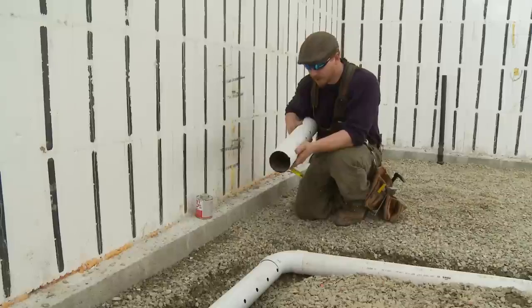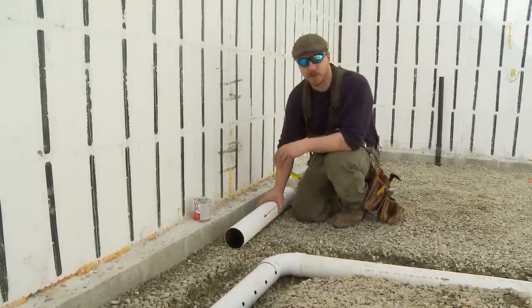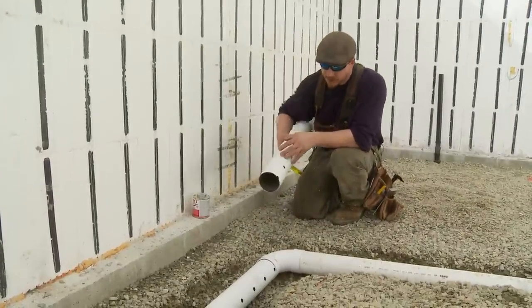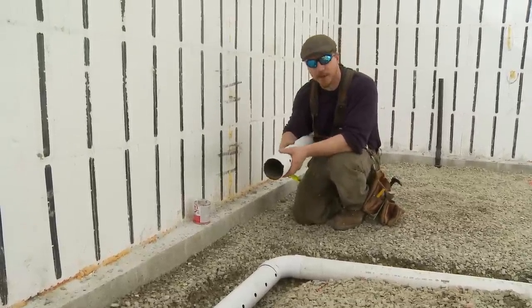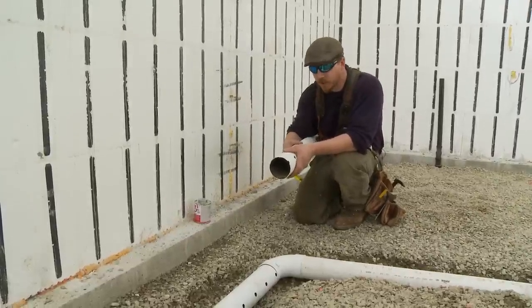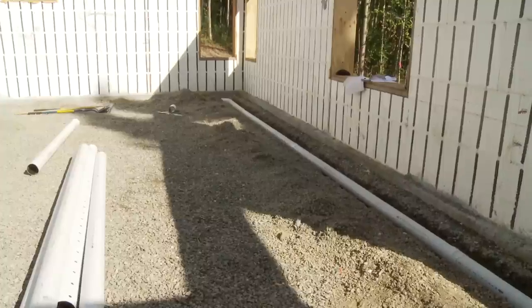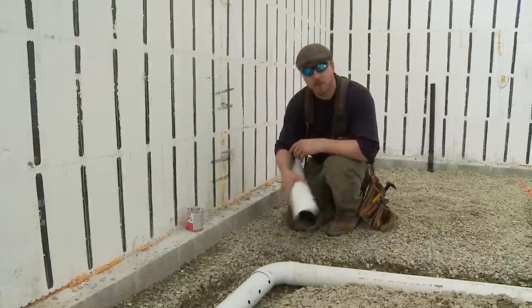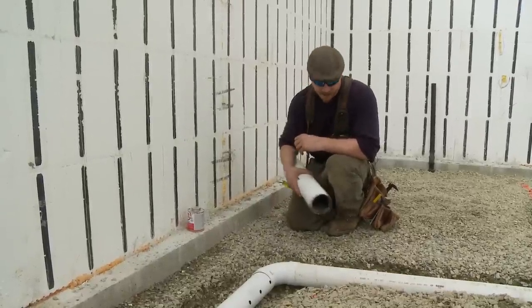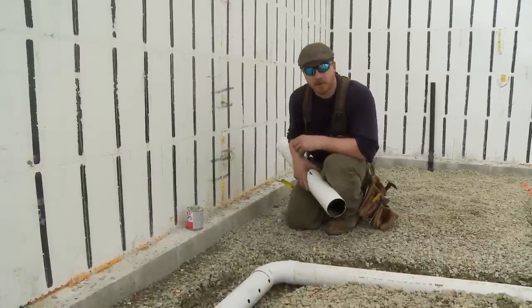The main thing when selecting this type of pipe is that it should have the compressive strength to handle loading above it, such as dirt in a leach field or in our case under a slab. The EPA suggests that for any slabs under 2,000 square feet you can use either three-inch or four-inch drain pipe, and anything between 2,000 and 4,000 square feet you should upsize to four-inch. I personally don't think you can go wrong with four-inch — even though our square footage is less than 2,000 square feet, we do have a significant number of 90-degree angles and other bends, and every time you introduce a bend you reduce airflow. Given that four-inch pipe only costs a little bit more, it gives a lot more peace of mind knowing you can move more air through the larger diameter pipe.